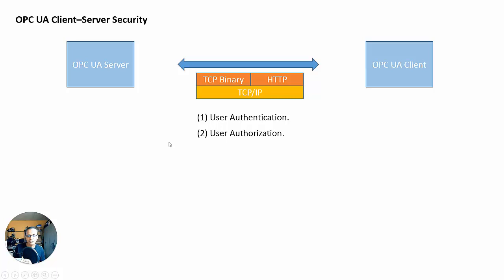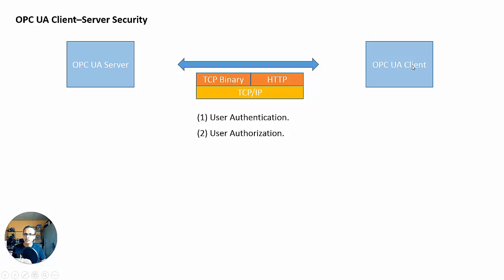Then there's user authorization, which is just your security level. For example, you have a laptop from work but the IT department doesn't allow you to install any software on it. Your user authorization level is not high enough to install software — IT has to give you an admin level. For OPC UA client to server, the client might not be able to write to the server, might be able to read stuff but not write it. Or another authorization level might mean the client can only read a certain portion of the data within the OPC UA server's information model. You can set those rules and security levels in there.